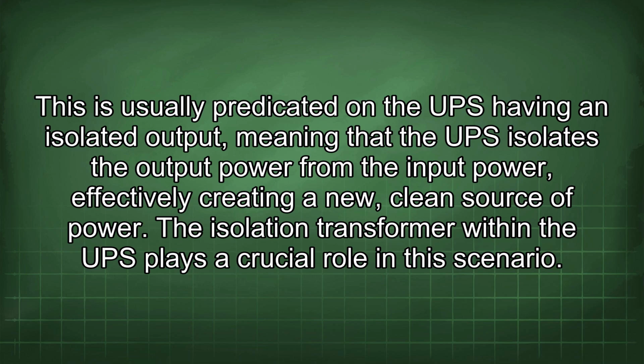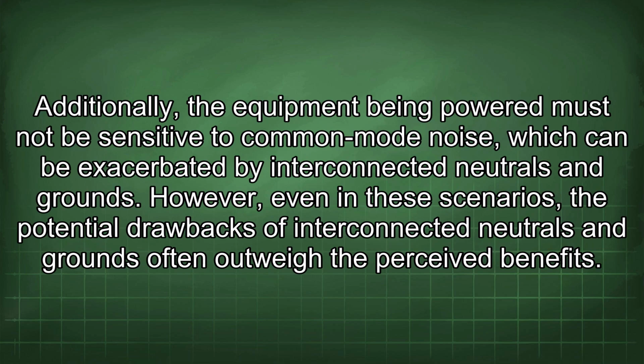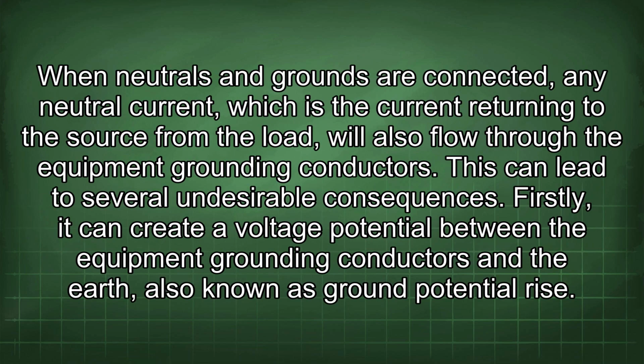The isolation transformer within the UPS plays a crucial role in this scenario. Additionally, the equipment being powered must not be sensitive to common mode noise, which can be exacerbated by interconnected neutrals and grounds. However, even in these scenarios, the potential drawbacks of interconnected neutrals and grounds often outweigh the perceived benefits. When neutrals and grounds are connected, any neutral current, which is the current returning to the source from the load, will also flow through the equipment grounding conductors. This can lead to several undesirable consequences.